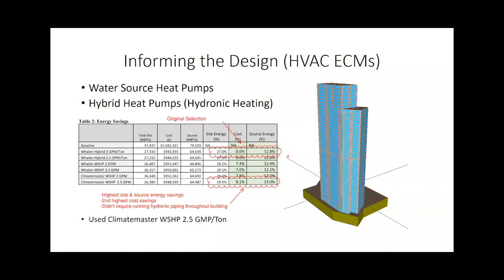But if they'd gone with a hybrid system that had the hydronic heating, that would have meant they would have had to run hydronic piping throughout the entire building, run hydronic piping into every single unit, and also have a massive base building boiler that would have supplied the hot water to all those systems. So that was a huge added cost to run all that piping and have that big boiler, compared to just using the traditional water source heat pumps, where it inherently has a condenser water loop that can be used for both heating and cooling.